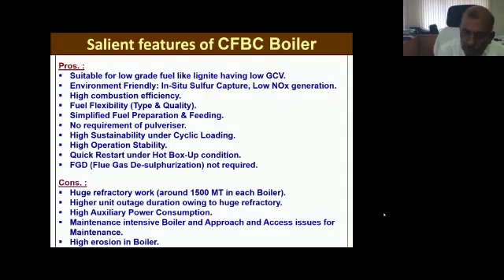Low NOx generation is mainly on 3 accounts, what we call the 3 T's: temperature, time, turbulence, which are key for the boiler performance. Temperature here is in the range of 850 to 900 degrees centigrade. So this temperature doesn't support NOx formation, so NOx is very low. Apart from this, on the air side also, we supply primary air, and for staged combustion we provide secondary air, which controls the NOx further.